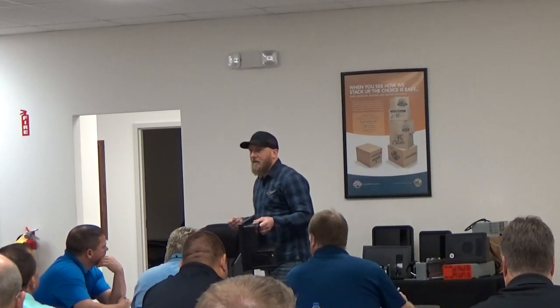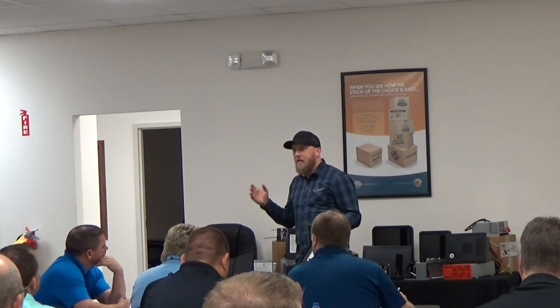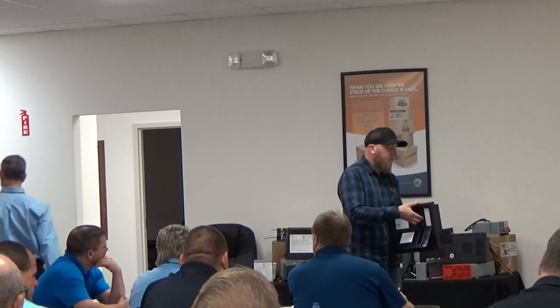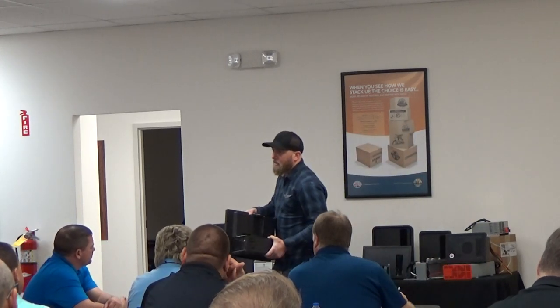The 65 and 75 are kind of getting blown off to the side now that people are using LED lighting, and the loads are a lot less than they used to be when you had incandescent bulbs. So a lot of what you're going to see now is about 55 amp and below. But our 55 amp does vent through the back, so you do need space behind these.